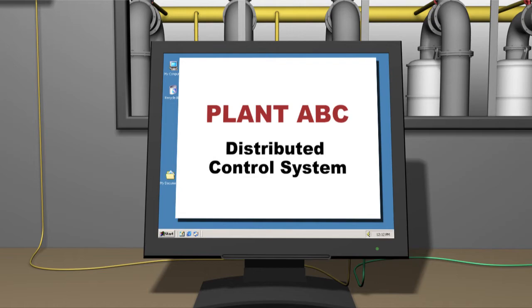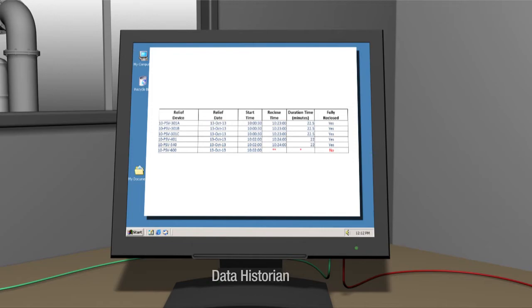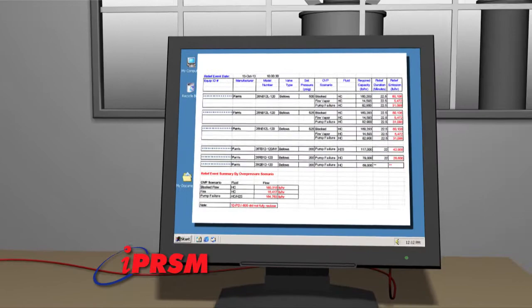Timestamp and stem position data, as provided by the smart PRV, are fed into the network's data historian. iPRSM software is capable of taking the data from the historian and calculating the theoretical volume of process fluid discharged during the relief event.